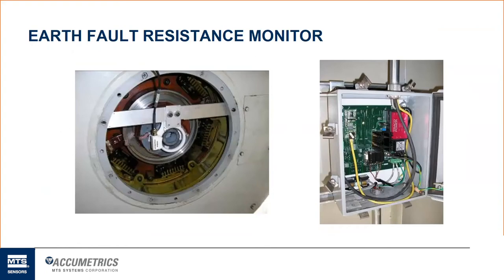You can see the gray transmitter is this piece that's mounted on the end of the rotor. There's a rotor end cap underneath. This is all standard stuff that would already be on any smaller air-cooled unit, and we can easily adapt our transmitter right in the center line, so that eliminates any balance issues, any concerns with high-speed vibration and things like that. We mount it right to the end of the shaft, and then we install the stationary pickup antenna, which is this white ring antenna.